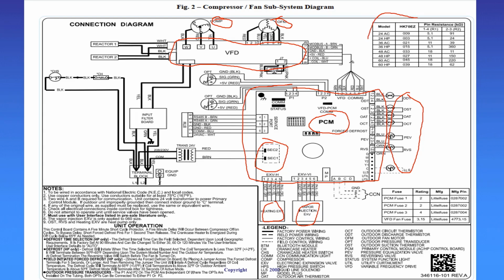You have some information regarding model plugs on the wiring diagram. You have information regarding the fuses. You have your legend that talks about all the components. You have your notes, which give you various wiring and other considerations. And then you also have a little bit of a unit operation explanation here at the bottom that tells you how the defrost time works and how the defrost is initiated and concludes. It also talks a little bit about the pressure transducers. So there is a lot of information on the current wiring diagrams, and it is very important that you as a technician are able to properly read and interpret these diagrams to help in your troubleshooting of the system.